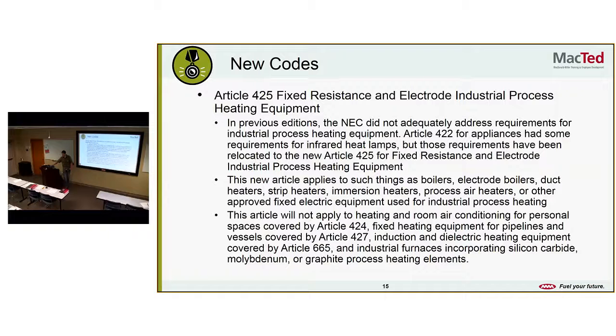It'll help to apply to things such as boilers, electrode boilers, duct heaters, strip heaters, immersion heaters, process air heaters, and other approved fixed electric equipment. So Article 425, remember that if you're working on any electric process heating equipment. It will not apply to heating and room air conditioning equipment for personal spaces. That's still going to be 424. So it's just process heating.